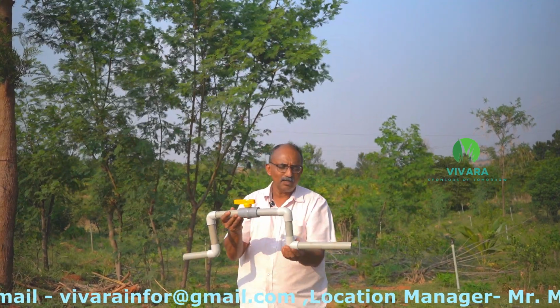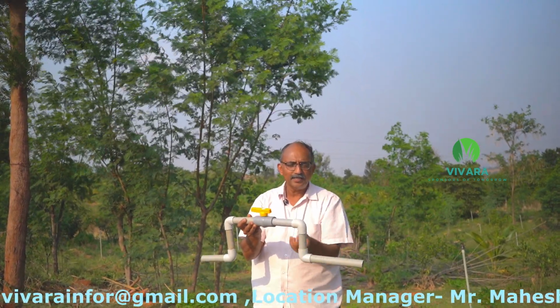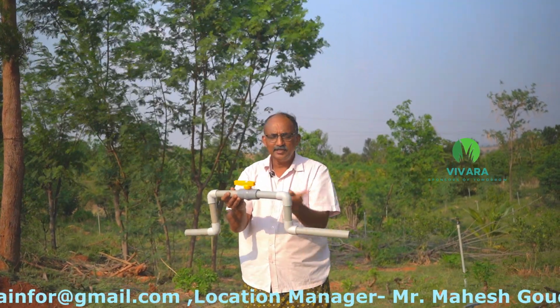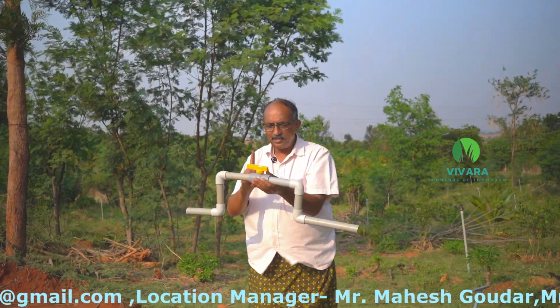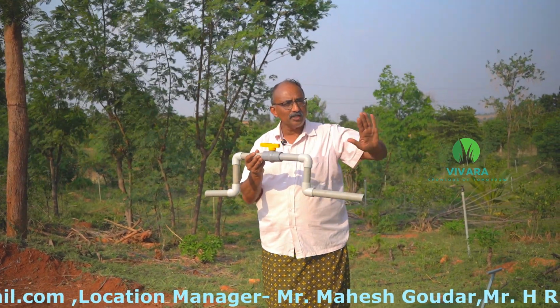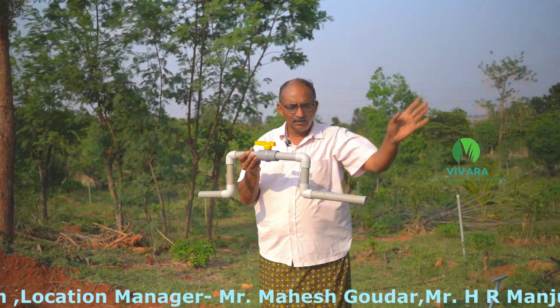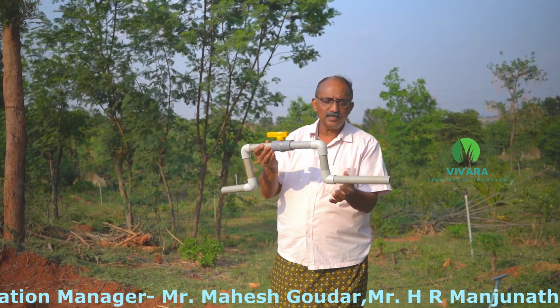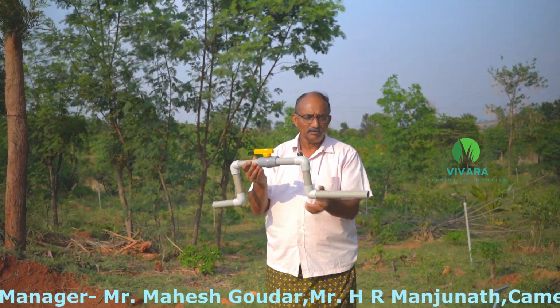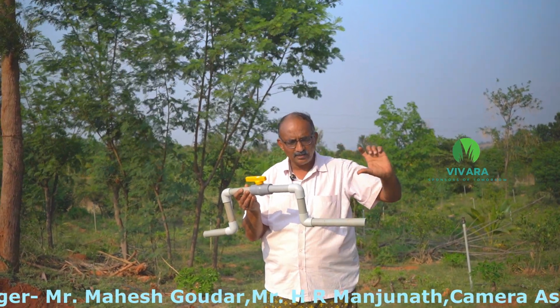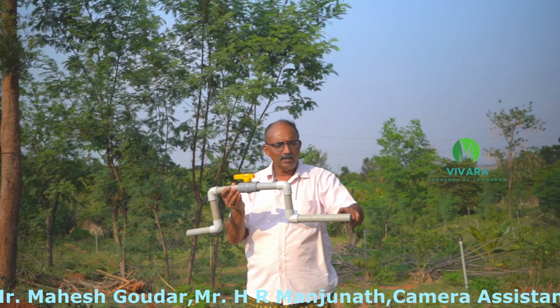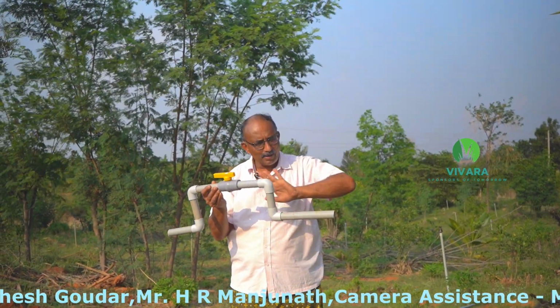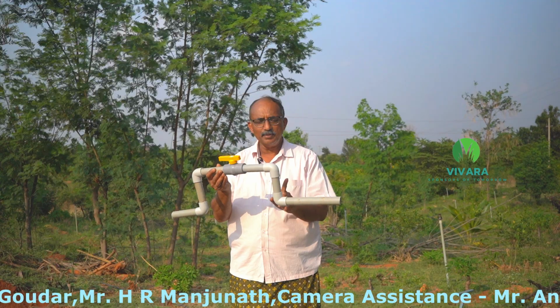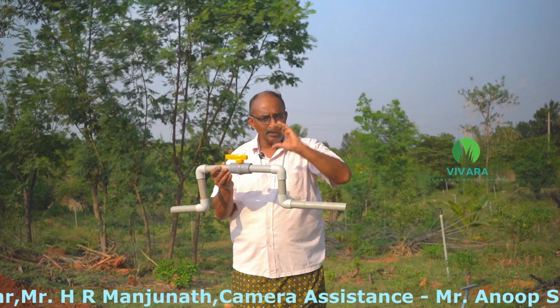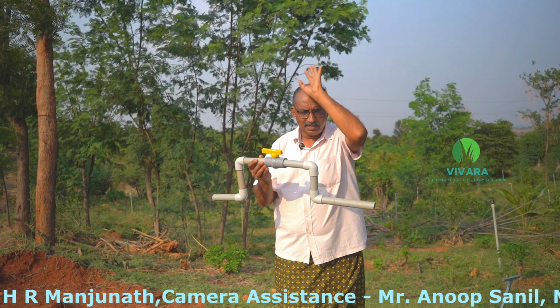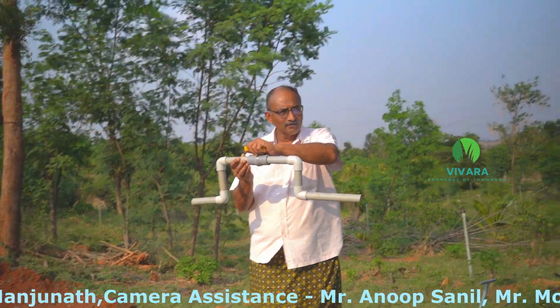Each elbow makes the water take a 90-degree turn. Four times the water has to take a 90-degree turn and then move out. This definitely creates back pressure on my motor. The theory suggests that each elbow will put a pressure of 3 feet head height. If my motor is operating at a certain head height, every time you introduce an elbow like this, it puts a backward pressure of 3 feet. In this example, 4 into 3, 12 feet of the motor's head height is used to introduce this valve.